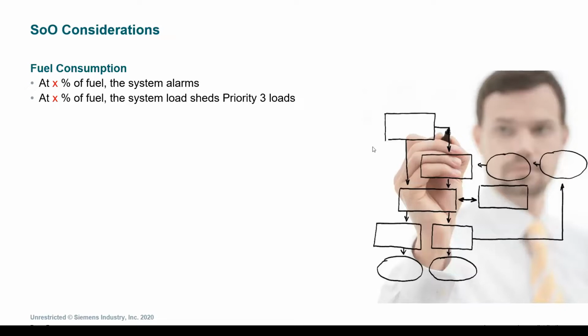When we look at the sequence of operations developed, we want to make sure we're looking at the system holistically. So for instance, when we look at the percentage of fuel being utilized, we want to make sure we understand that along with the consumption rate of the generators and the anticipated demand of the load. And we want to make sure at a certain percentage, it alarms to the facilities team to make sure that fuel delivery is coordinated. And if it's not done in a certain amount of time, then at a lower percentage, the system starts to shed load if that's necessary for an extended outage.